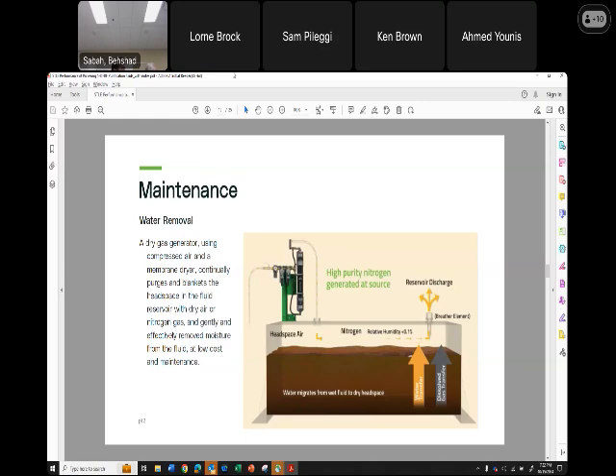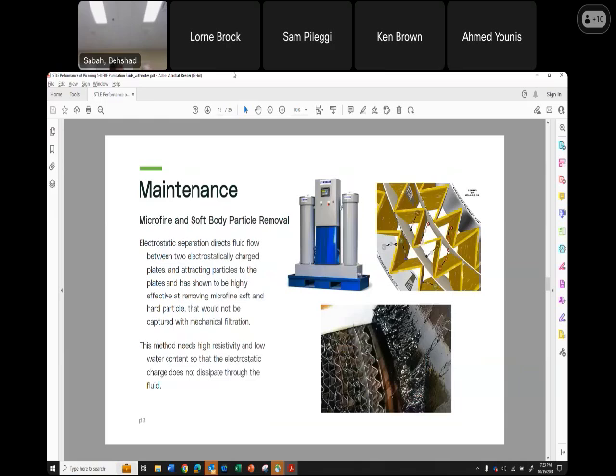So we're at 600-700 ppm moisture, very easy to bring that moisture down to between 200-300 ppm water. Next. Okay, so electrostatic separation, basically we maintain a high voltage between two charged plates with an absorbing media. Charged particles are pulled one way or the other towards the plate and get caught in the absorption media.